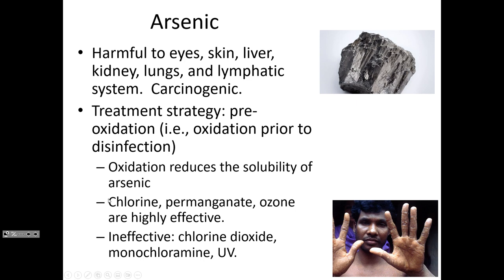Probably the most common way of removing arsenic is called pre-oxidation. You may wonder why it's called pre-oxidation — that is because oxidation is going to occur at the disinfection step, but pre-oxidation means you're adding an oxidant prior to most of the other steps, meaning coagulation, flocculation, settling, and sand filtration. So if you oxidize the water before all those steps, it will take the arsenic out of solution.